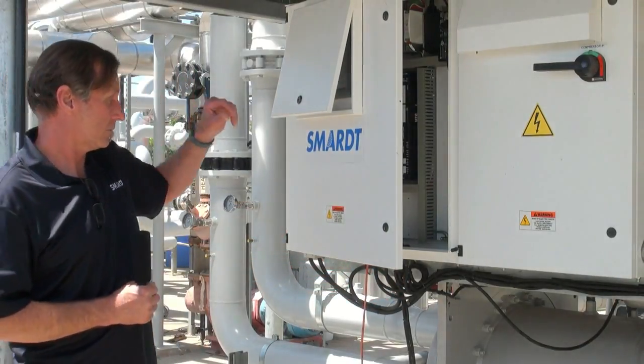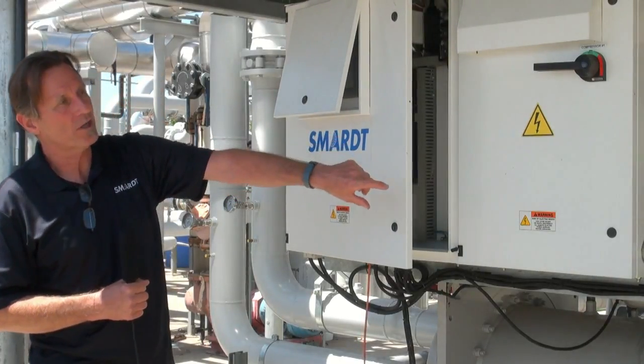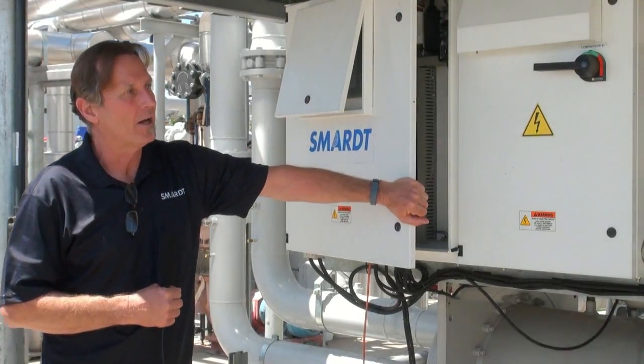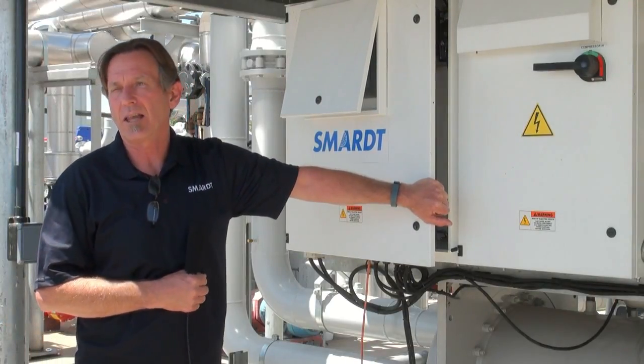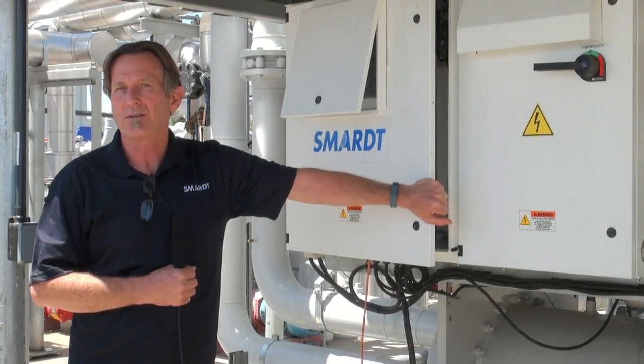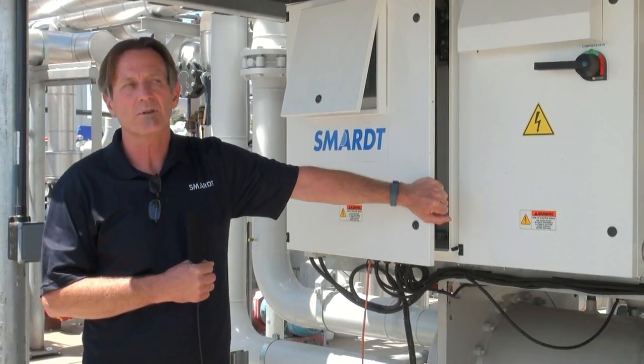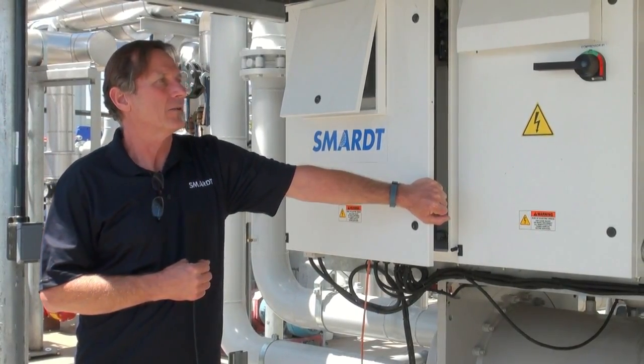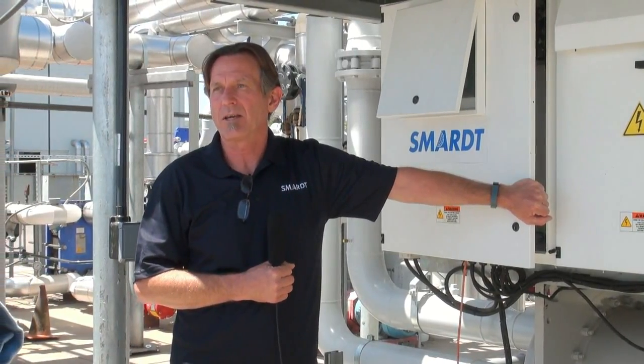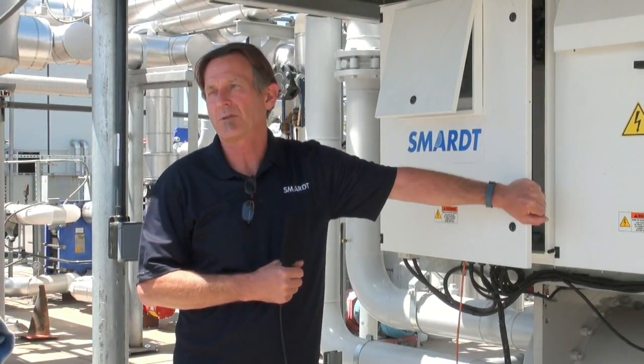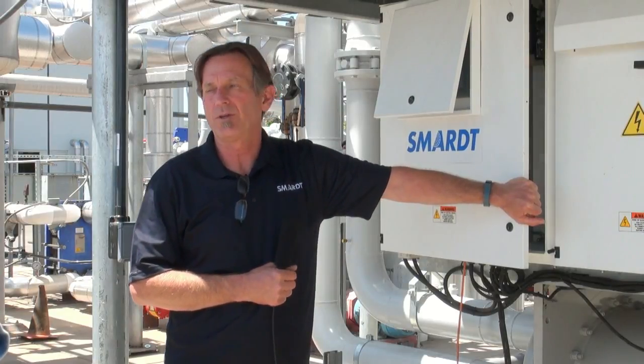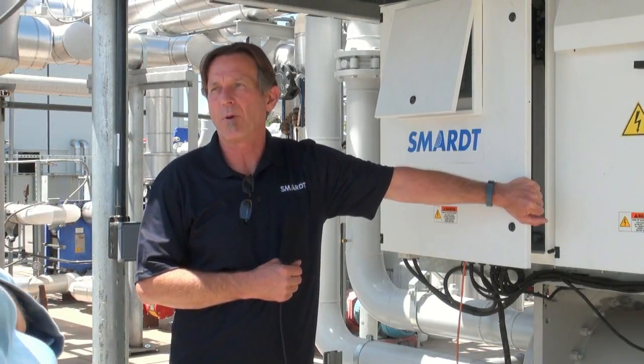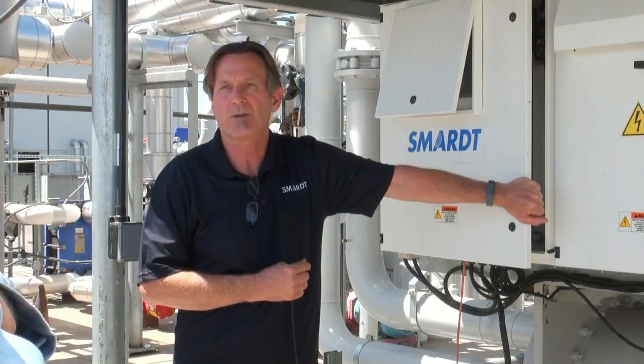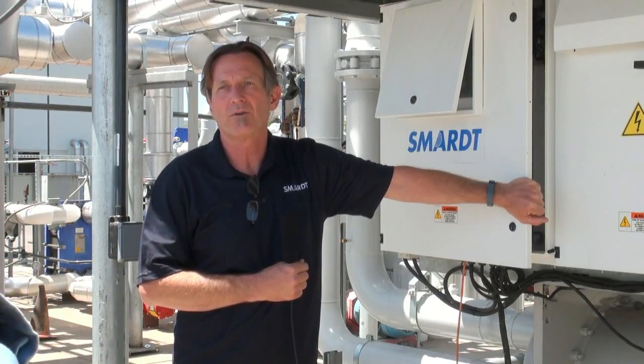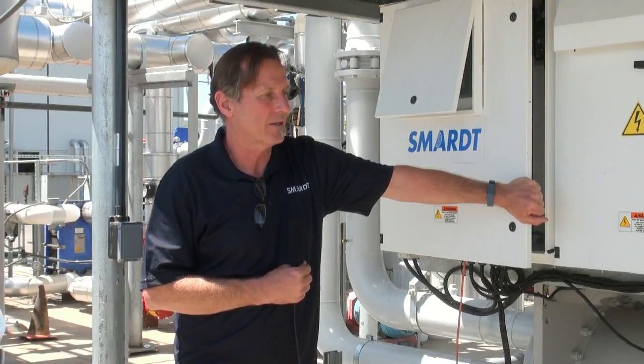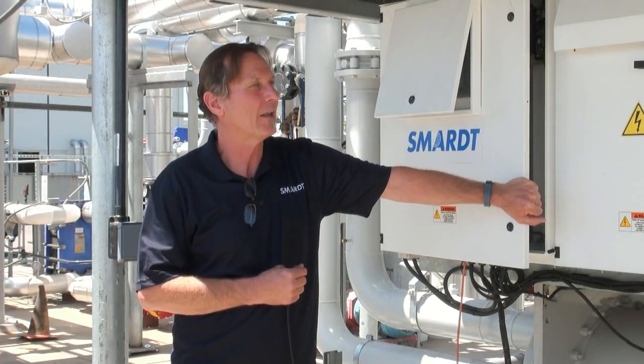We've got the two disconnects, one for each compressor. You can isolate the compressor electrically. You can also isolate each compressor from the refrigerant system. So you can basically isolate the compressor electrically and from the refrigerant system to work on it. So you can continue to run the chiller even though you may have a problem with one compressor. If you want to service one compressor on its own and not shut the chiller down, you can do that. So you've got a number of valves on here to allow you to do that.